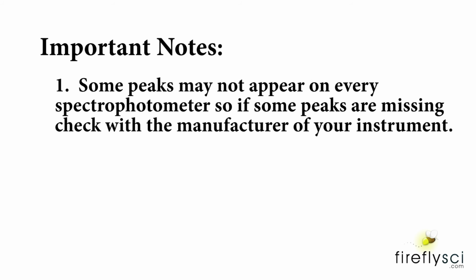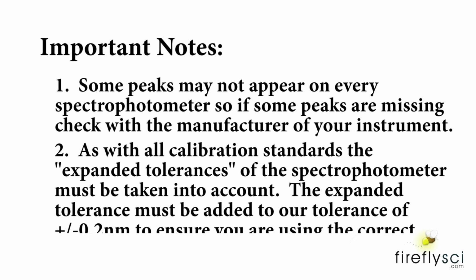So just some important notes. Some peaks may not appear on every spectrophotometer, so if some peaks are missing, make sure you check with the manufacturer of your instrument. As with all calibration standards, the expanded tolerance of the spectrophotometer must be taken into account. The expanded tolerance must be added to our tolerance of ±0.2 nanometers to ensure you are using the correct data.